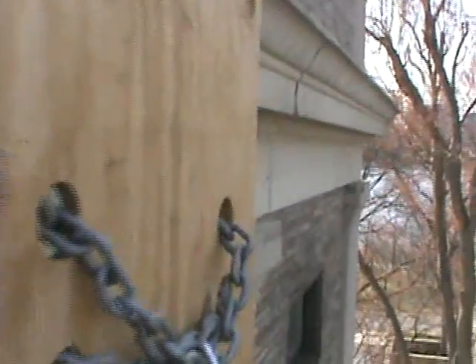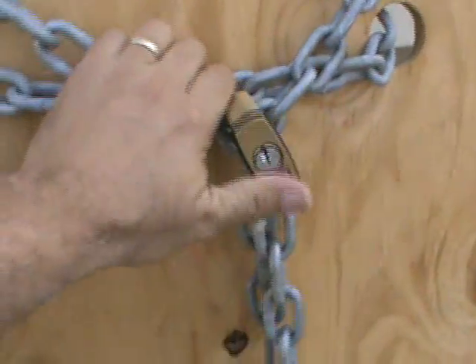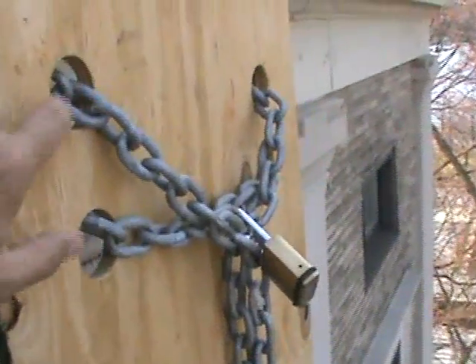This wood piece here on this fire escape, if you're going to block this just for access for the vendors, you have to make sure the firemen don't want to use the same ladder. So this would be an obstruction for the firemen. We have to discuss that with the fire department as to whether or not this is a concern of theirs. But if this is allowed, you want to put a piece of metal here. It can't be something combustible, something that will catch somebody's eye. So even though you're having some issues with the students, there might be other ways to deal with that.